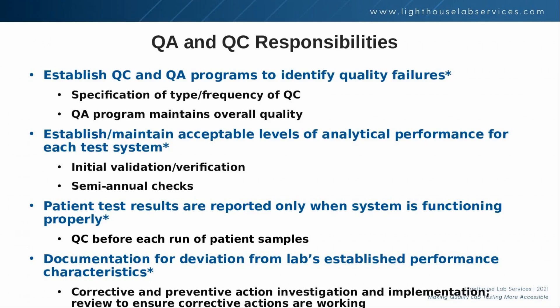The lab director must maintain acceptable levels of analytical performance. This is done through the initial method verification or validation and semi-annual checks, which include proficiency testing at minimum. It's important for the lab director to make it clear to all lab staff that patient results can only be reported when the test system is in check, and one of the easiest ways of making sure this is the case is through running QC prior to any patient samples. If QC fails, this is a pretty good indicator that there is an issue with the system that needs to be addressed.